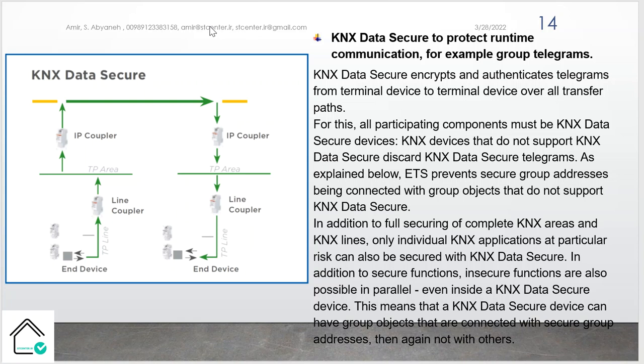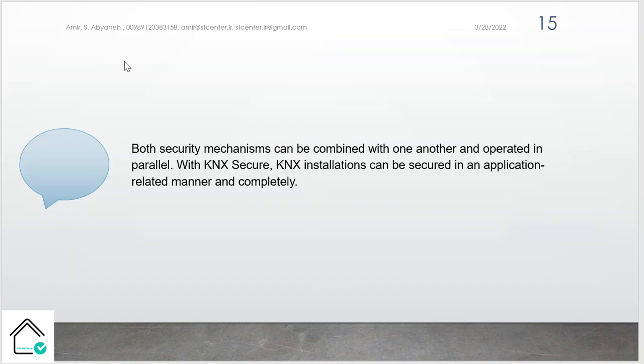For this, all participant components must be KNX Data Secure devices. KNX devices that do not support KNX Data Secure discard KNX Data Secure telegrams. As explained below, ETS prevents secure group addresses from being connected with group objects that do not support KNX Data Secure. We will see this shortly in the ETS. Both security mechanisms can be combined with one another and operated in parallel. With KNX Secure, a KNX installation can be secured in an application-related manner and completely. So it's possible to have KNX IP Secure, KNX TP-to-TP Secure, KNX TP-to-RF Secure, and so on. Good.